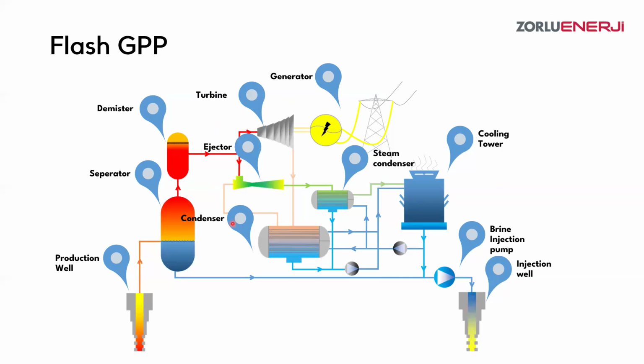Okay, and in here we are seeing the other auxiliary equipment. First, we have ejectors or the vacuum system. There could be some vacuum pumps or any other equipment to provide that service as well. In here, you are seeing that equipment because after the steam, or the steam and gas, gets into the turbine, after the generation, they go to another equipment which is called a condenser.